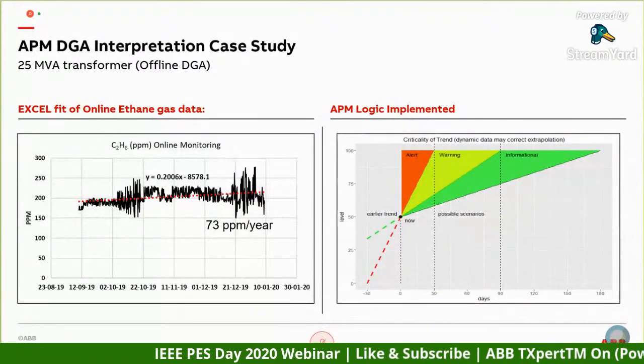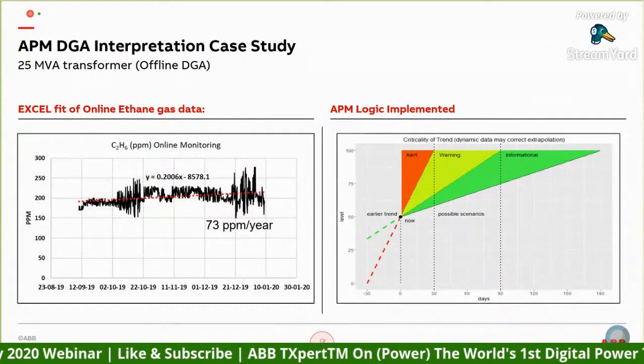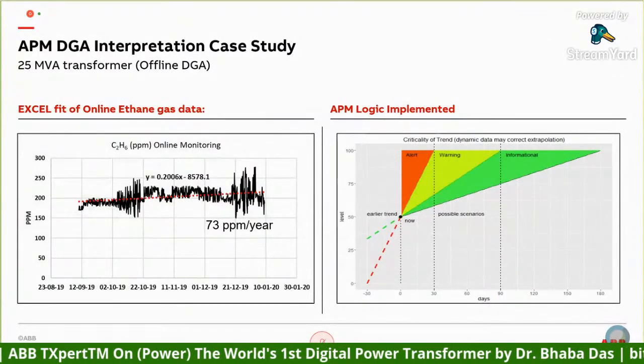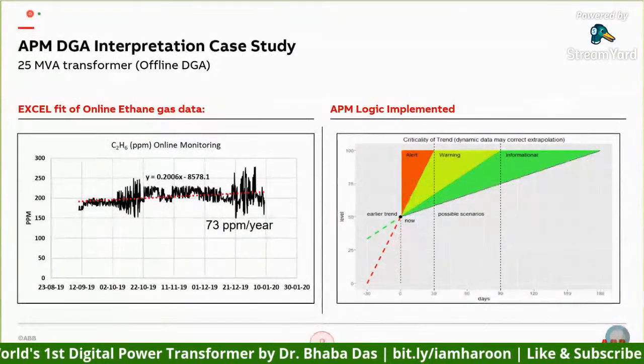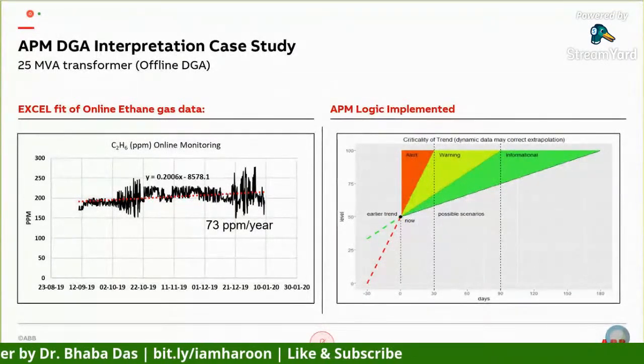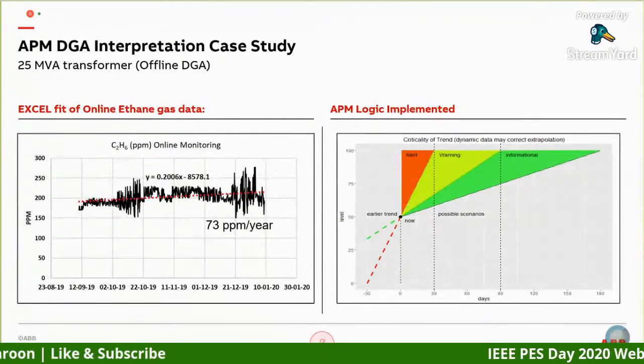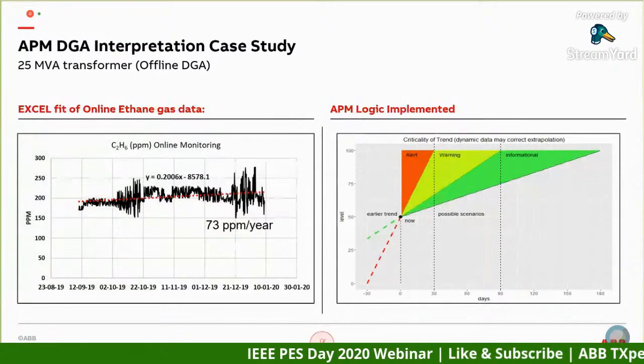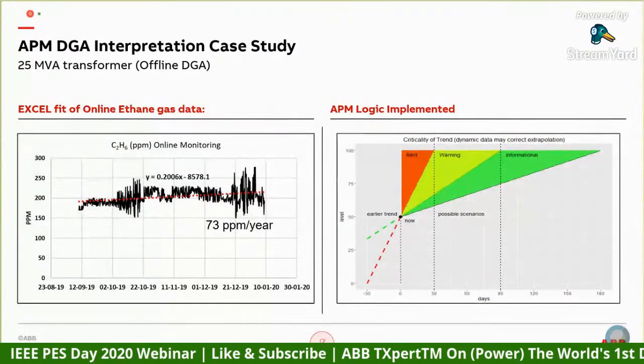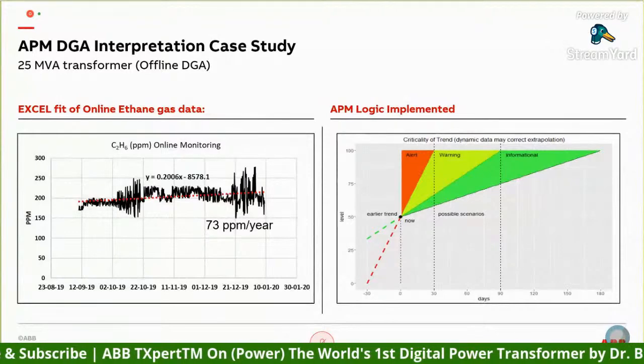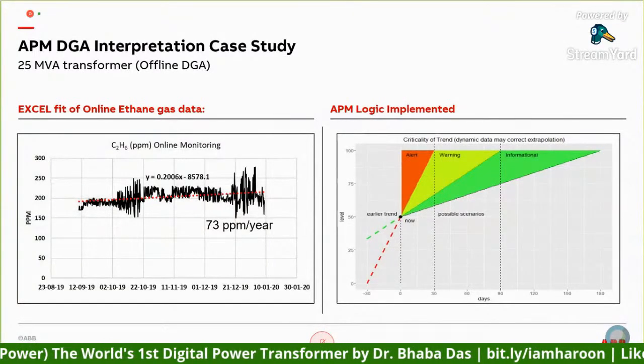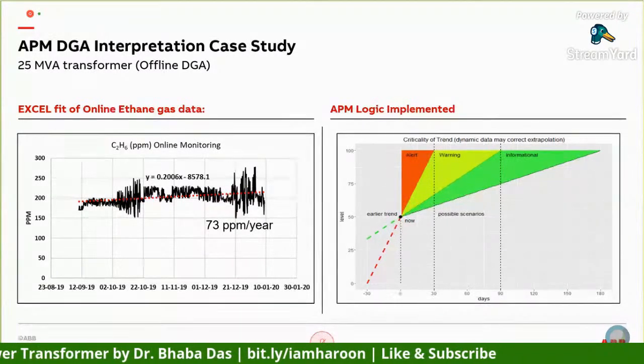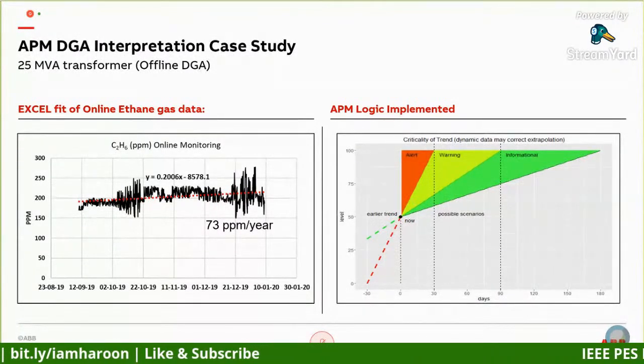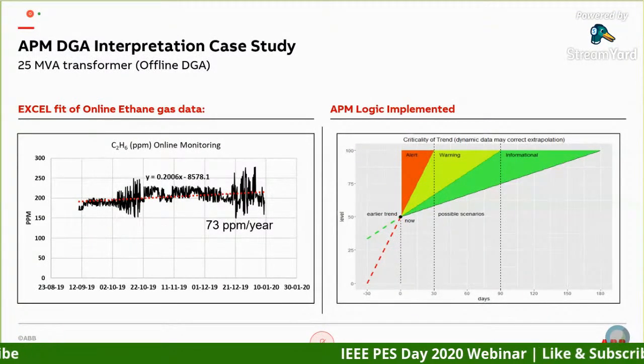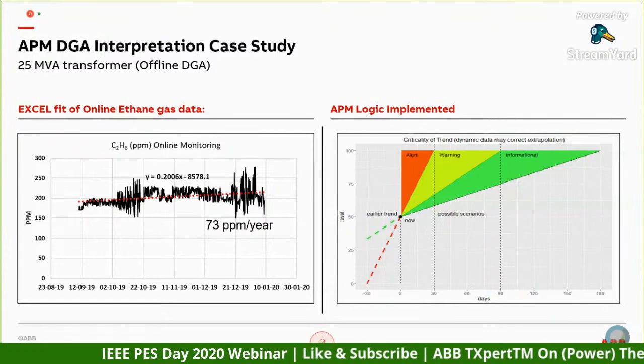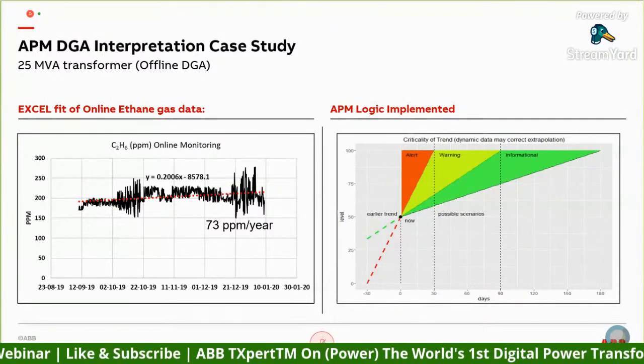So that is how we were able to do trending of the offline DGA samples, and based on that we told the customer that you will cross around 250 ppm in May 2020. The shutdown was planned in June to investigate based on what APM recommended. Once the lockdown in Singapore is over, I will try to find out whether the customer will shut down the transformer or not.